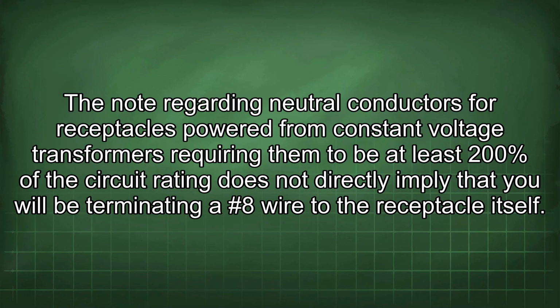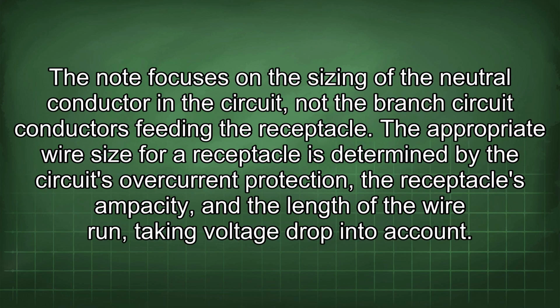The note regarding neutral conductors for receptacles powered from constant voltage transformers requiring them to be at least 200% of the circuit rating does not directly imply that you will be terminating a #8 wire to the receptacle itself. The note focuses on the sizing of the neutral conductor in the circuit, not the branch circuit conductors feeding the receptacle. The appropriate wire size for a receptacle is determined by the circuit's overcurrent protection, the receptacle's ampacity, and the length of the wire run, taking voltage drop into account.